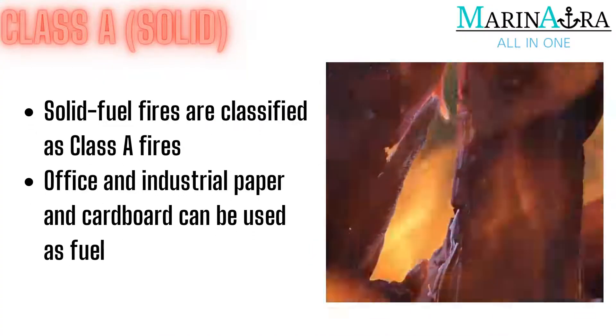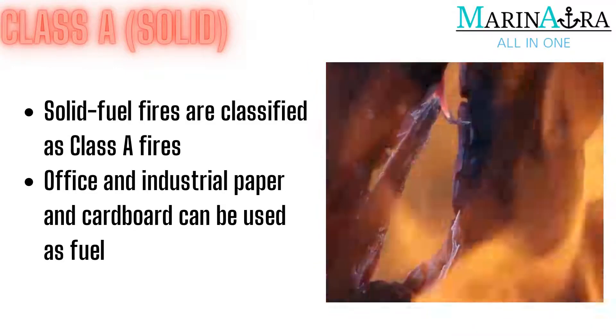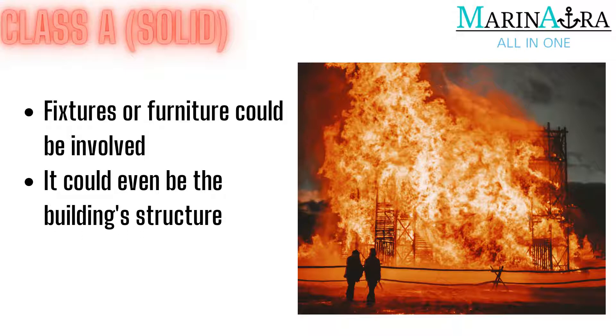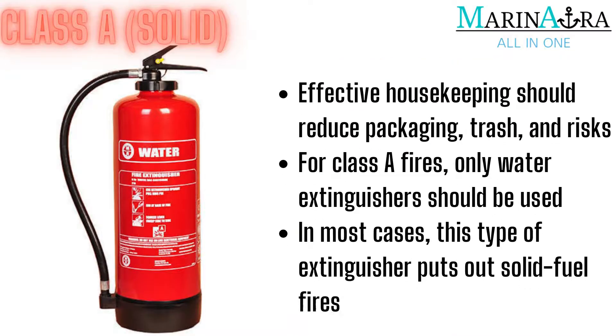Class A — Solids. Solid fuel fires are classified as class A fires. Paper and cardboard, which are commonly used in offices and industries, could be used as a source of fuel. Furniture, fixtures and fittings, or even the building structure itself could be involved. Because solids are the most prevalent sort of fuel, this is one of the most common types of fire. Good housekeeping should aid in the reduction of materials such as packaging and garbage, hence reducing risks. A water extinguisher is the only form of fire extinguisher that should be used on a class A fire, as it can put out most solid fuel fires. It should not, however, be used near electrical equipment because it is a conductor.